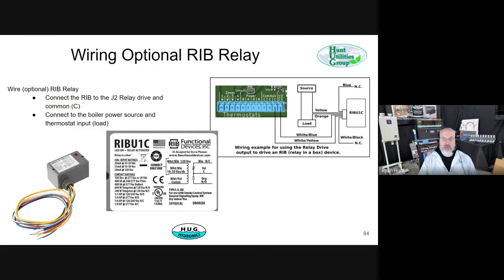A lot of boilers, if they're real boilers and not flow controlled, require a signal to tell them to turn on. So we use a RIB relay for that. The RIB relay takes an input on 2 wires from the relay driver output and the common, and then closes a contact that turns that boiler on. The RIB relay looks like that. RIB stands for relay in a box. It's just a relay in a nice little package that can handle a wide range of voltages and control functions.